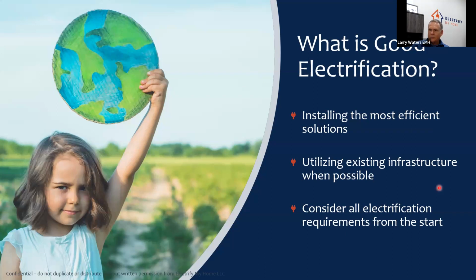And like we've said multiple times here, consider all the electrification requirements from the start. The reason we talk about this is every year we run into customers that got the wrong heat pump solution up front, and the HVAC contractor told them they needed an upgraded panel. Then we come in to do the rest of the electrification, and the contractor just upgraded the panel enough to fit their breakers in, maybe went from 100 to 125 and put 60 amps worth of load in there. And now the customer needs to upgrade again when they're going to the stove or the water heater. So we need to be careful about that. Consider all those requirements from the start. Our average system that we install in a typical 1,500 square foot house needs a 120 amp breaker to run the entire system. One circuit goes to the outside, and the outside powers the inside.